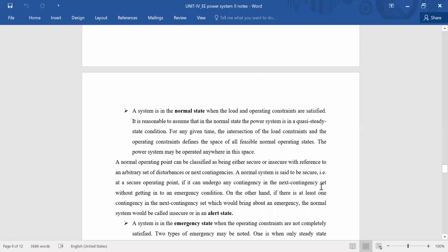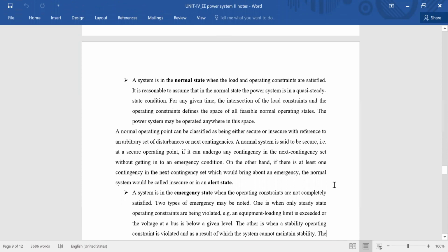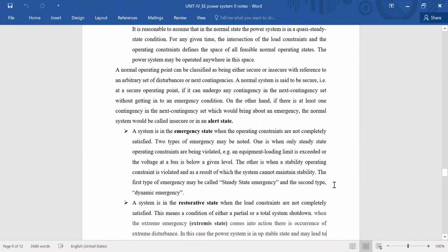In the emergency state, the operating constraints are not completely satisfied. There are two types of emergency: one is when only steady state operating constraints are violated, for example an equipment loading limit being exceeded or the voltage at a bus falling below a given level. The other is when the stability operating constraint is violated, and as a result the system cannot maintain stability. So the first type is the steady state emergency, and the second is the dynamic emergency.